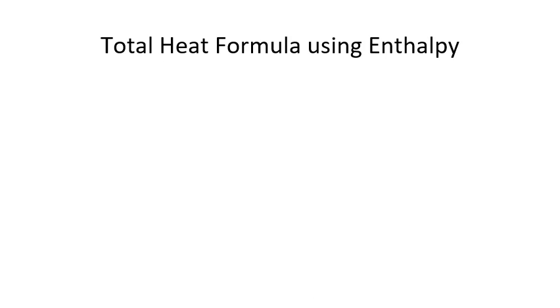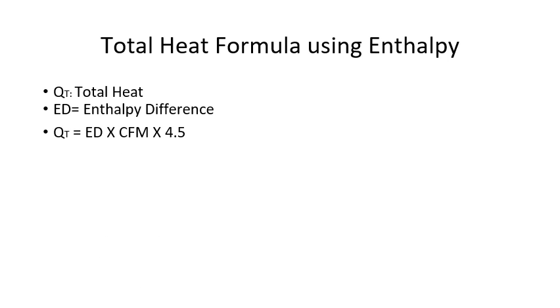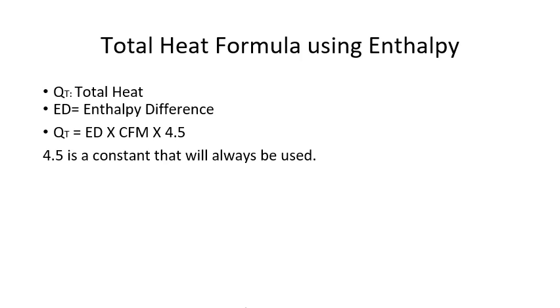Our total heat formula takes on the same structure as our sensible heat and latent heat formulas. We're looking for our total heat — QT in this example — and we need our enthalpy difference. Here's the formula: total heat equals enthalpy difference times CFM times 4.5. That 4.5 is a constant that will always be used. The sensible heat formula had a constant of 1.08, the latent heat formula had a constant of 0.68, and the total heat formula has a constant of 4.5. The structure is: difference of heat times CFM times a constant.